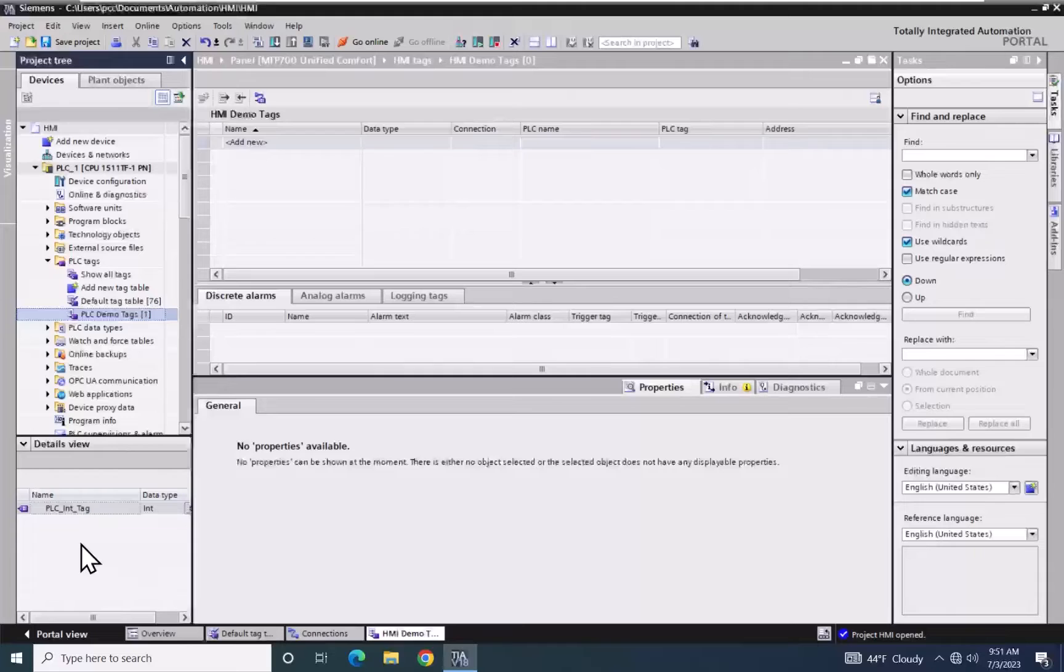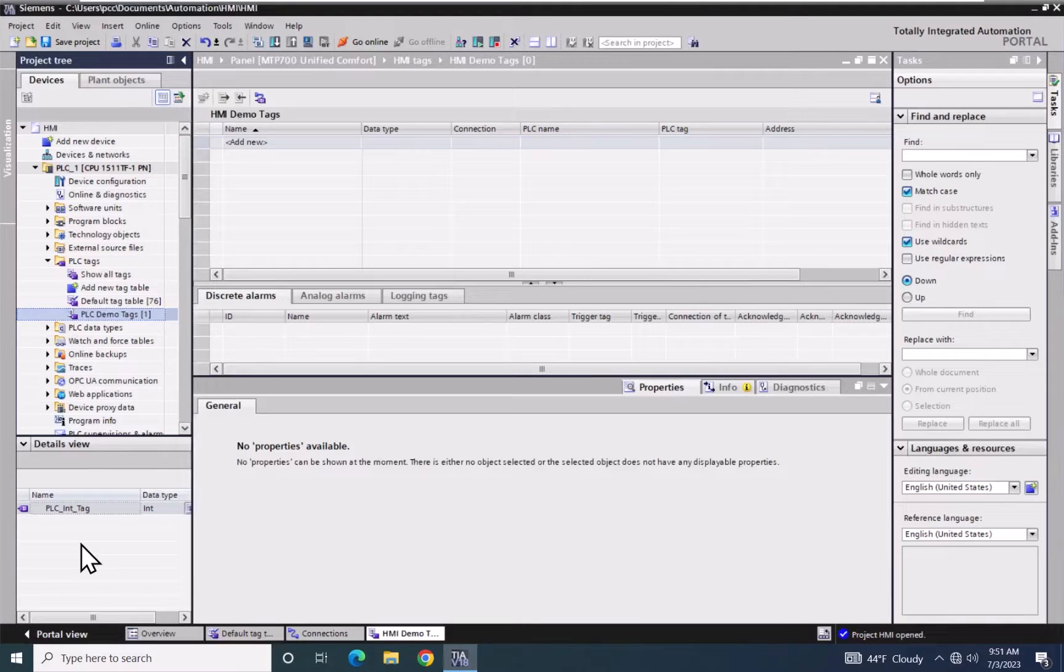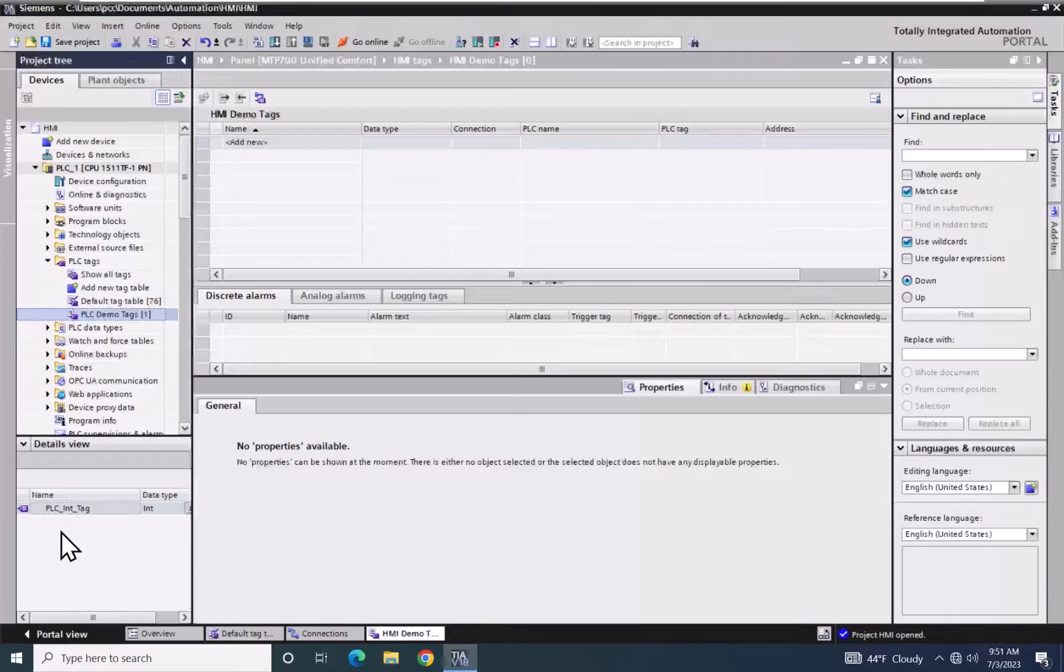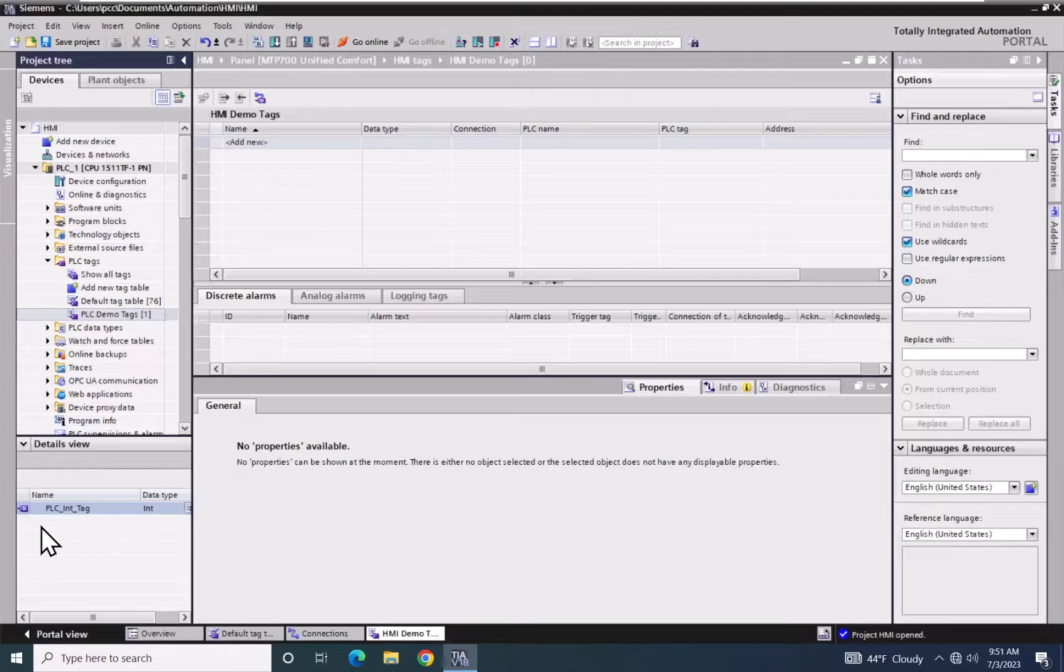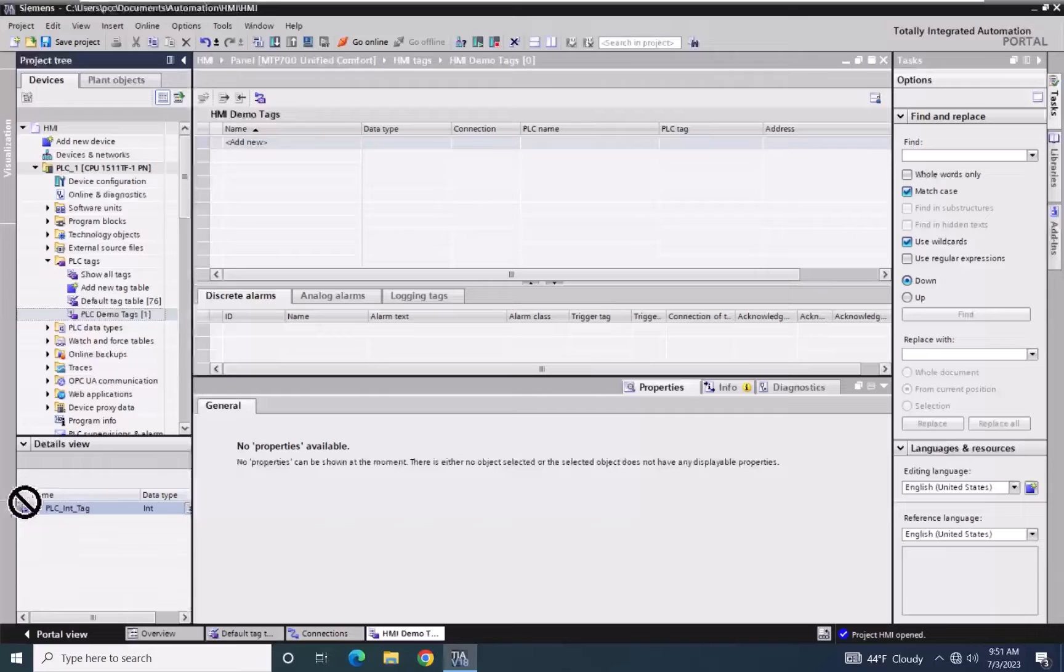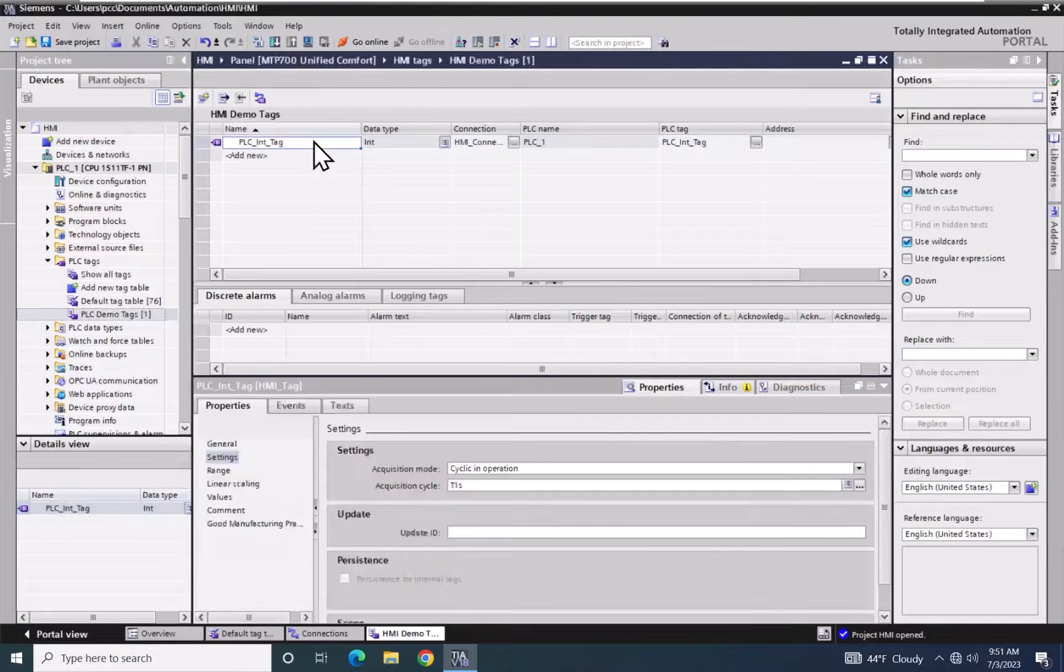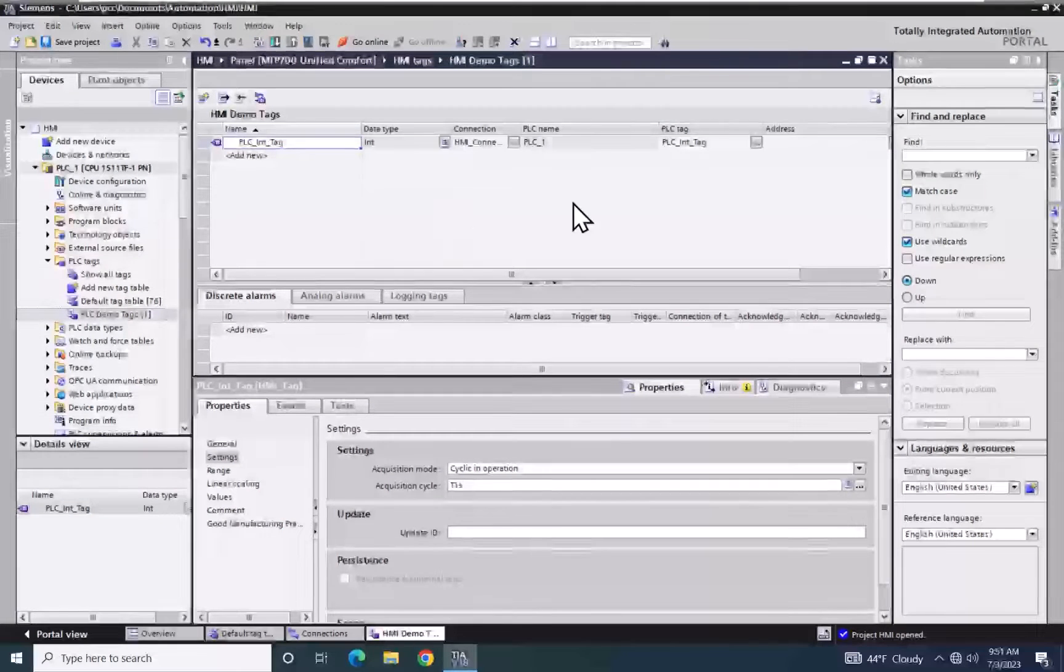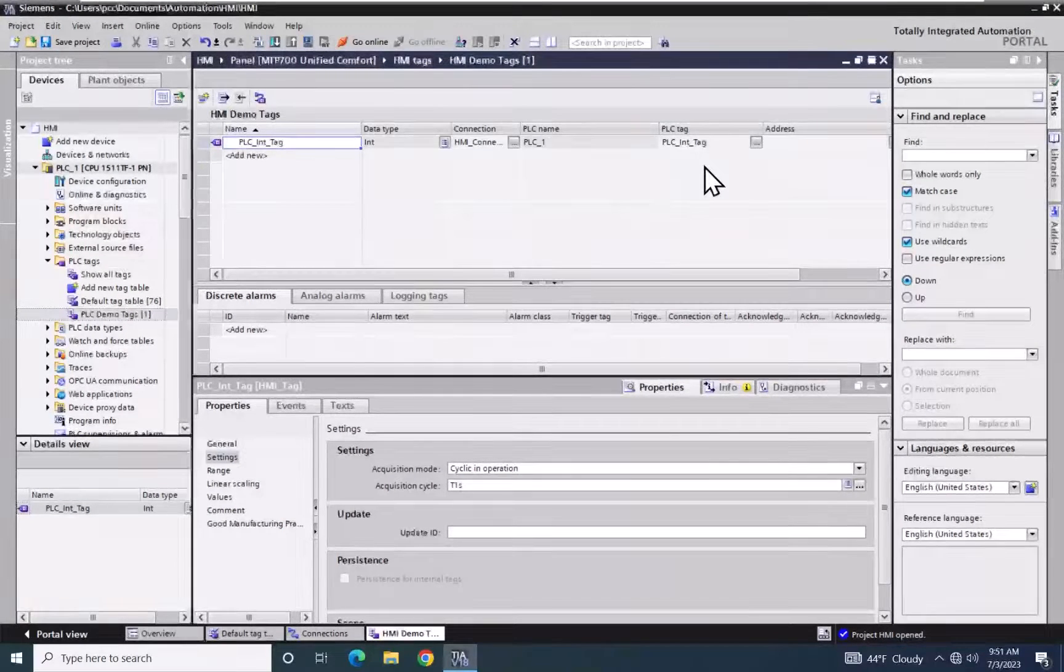You do have the option to bring in a single tag at a time, or you can select multiple tags and bring those into the HMI. Since I only have one tag created in the PLC in the PLC Demo Tags tag table, I'm going to select that one tag, and I am going to drag that into my HMI Demo Tags area. This will create an HMI tag that will point to the actual PLC tag.